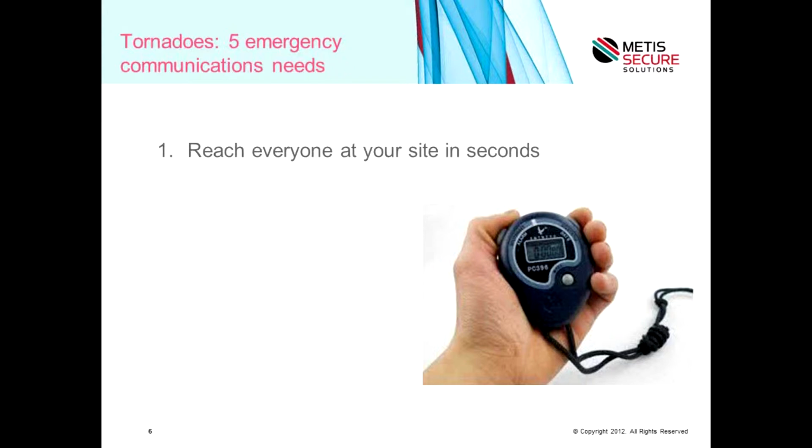Many people have traditional PA systems where they can make voice announcements on site, but these can also pose certain problems. Some PA systems only reach specific areas of a facility. In addition, they won't likely reach people in noisy areas such as industrial floors. They may also tie you to a specific announcement location, and that can be dangerous for the person assigned to making the announcement. And finally, if you have a multi-building site with separate PA systems in individual buildings, a tornado emergency may not give you enough time to physically go to each building to alert the people at that site.